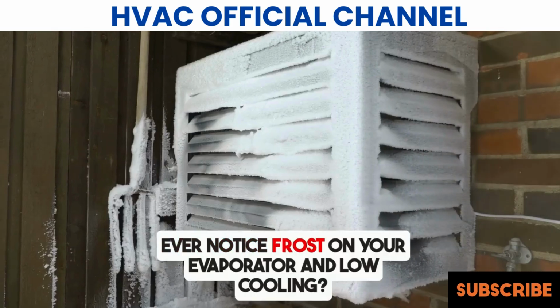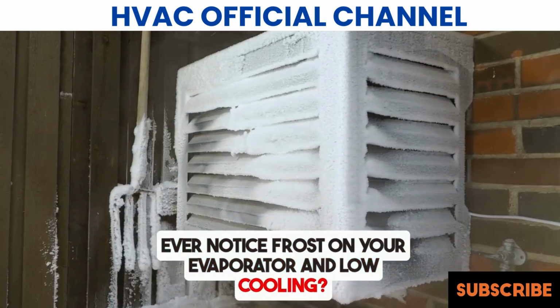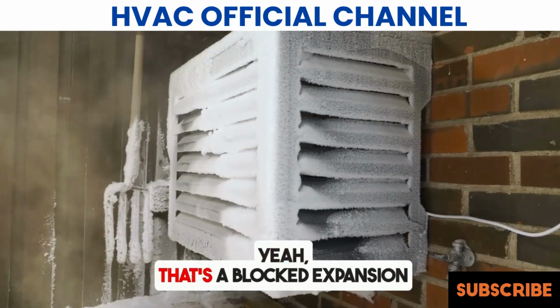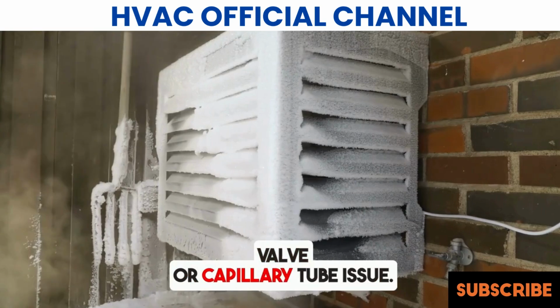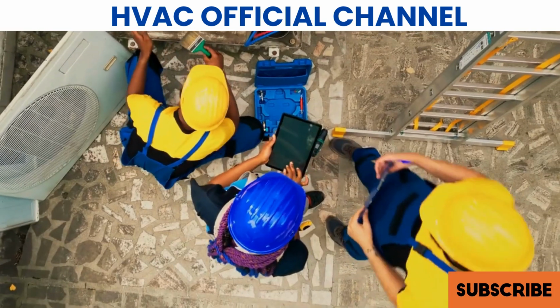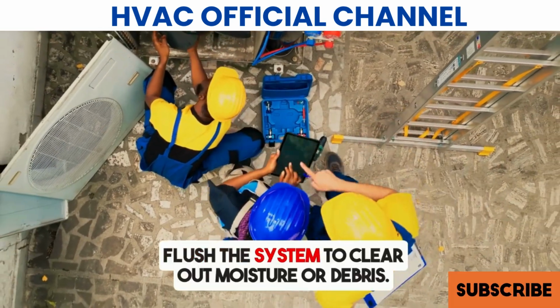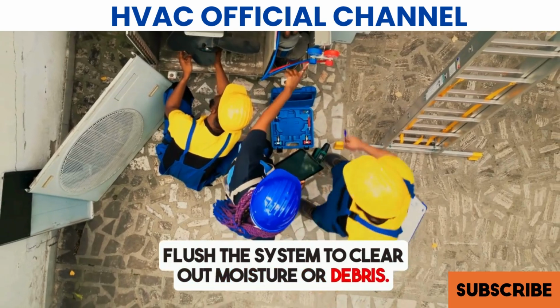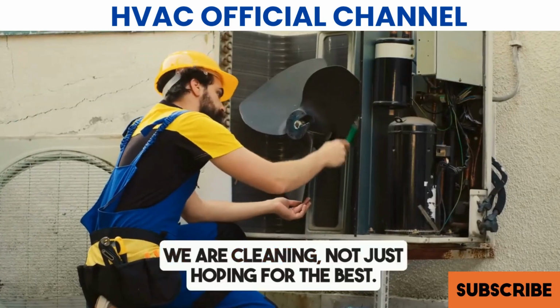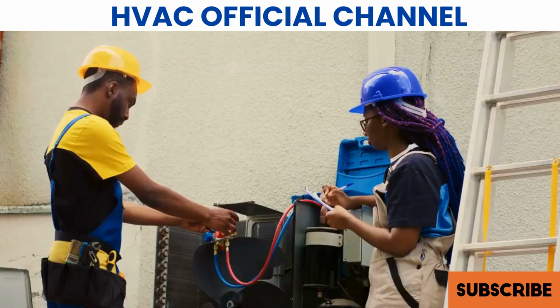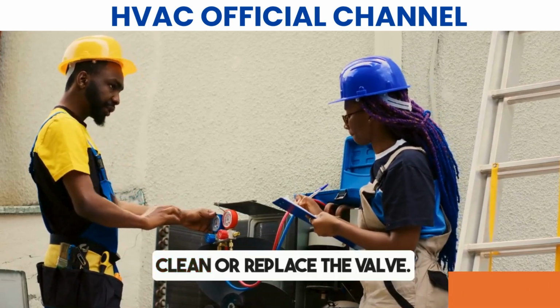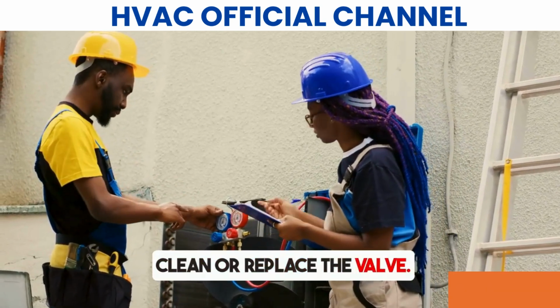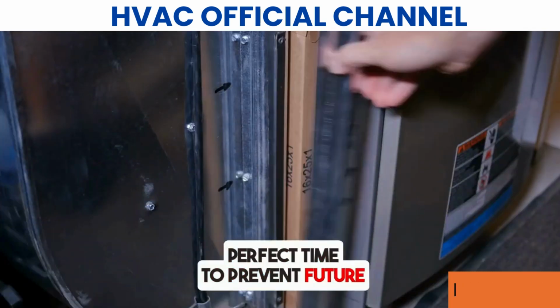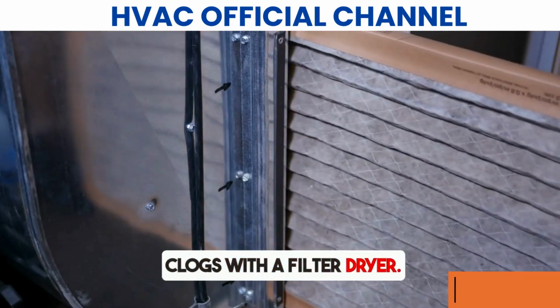Ever notice frost on your evaporator and low cooling? Yeah, that's a blocked expansion valve or capillary tube issue. Step 1. Flush the system to clear out moisture or debris. We are cleaning, not just hoping for the best. Step 2. Clean or replace the valve. Perfect time to prevent future clogs with a filter dryer.